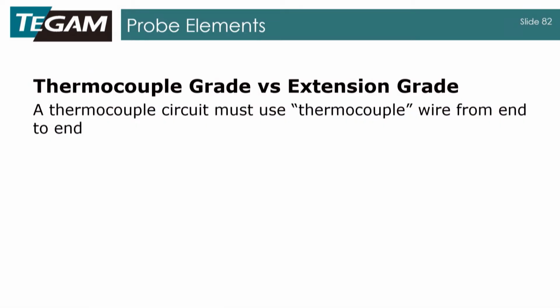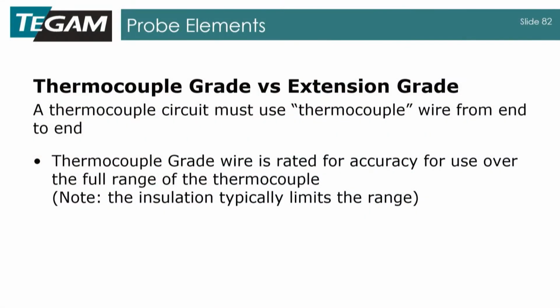So next I want to go over thermocouple grade wire versus extension grade wire. And basically, when you have a thermocouple circuit between your instrumentation and your thermocouple probe, the entire length has to be thermocouple wire, and that means that the wire is made up of those two dissimilar metals that your thermocouple is made up of. So thermocouple grade wire is rated for accuracy over use of the full range of the thermocouple type.